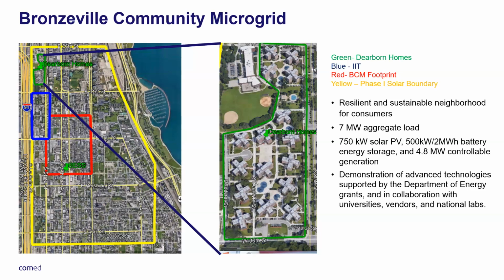Within the Bronzeville Community Microgrid, we deployed a microgrid management system provided by Siemens. We have 7 megawatts of aggregate peak load in the microgrid, along with 750 kilowatts of solar PV, 500 kilowatts, 2 megawatt-hours of battery energy storage, and 4.8 megawatts of controllable generation.